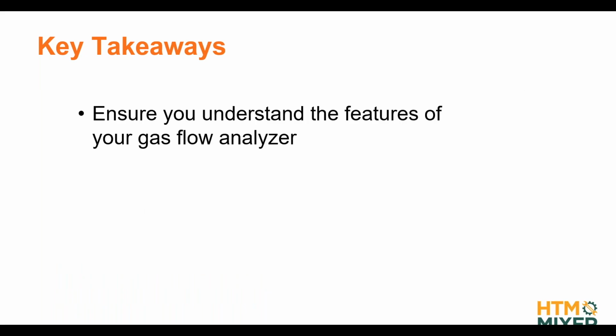All right. Any questions? Before we summarize, the key takeaways from my point of view: number one, ensure you understand your gas flow analyzer. Make sure that you study the manual and make sure you understand, for example, what is being measured in the main flow channel, and even more important, what is not being measured there. Where do you have to, for example, key in pressure or have an additional module for your oxygen or whatever. That's really important to make sure that you understand how your setup is going to look.